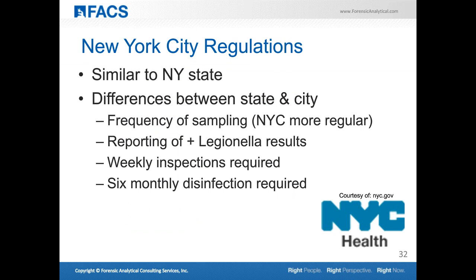New York City also implemented their own regulations, very similar to New York State, though there are some general differences. New York City requirements require more frequent sampling, and do require reporting of positive Legionella results to the Department of Public Health agency. Weekly inspections are required, along with six-monthly disinfection with a written report detailing the disinfection procedures performed for cooling towers. So those are some of the differences between state and city regulations.